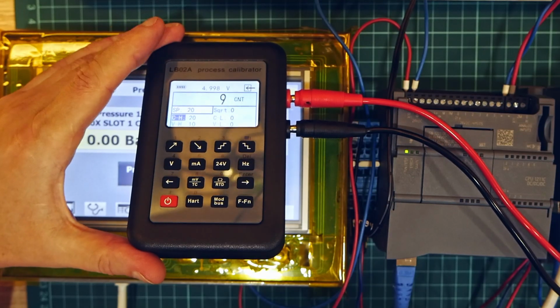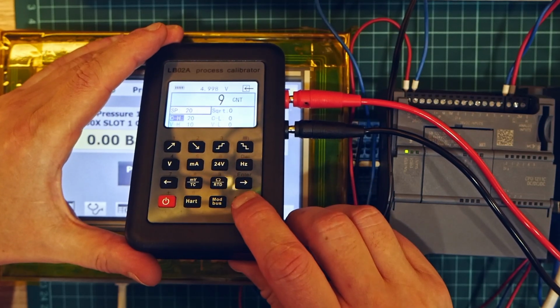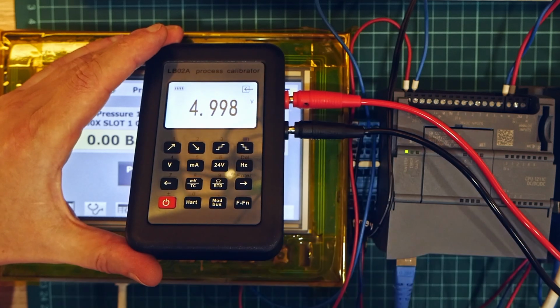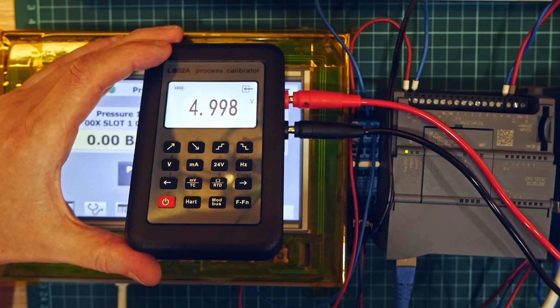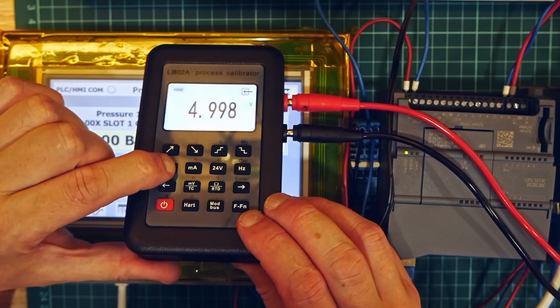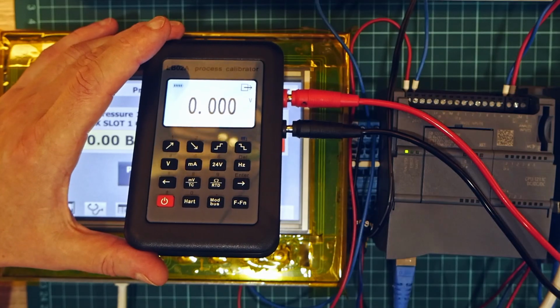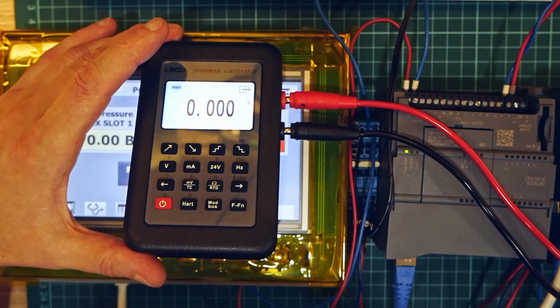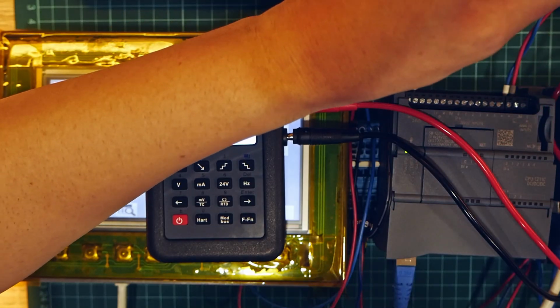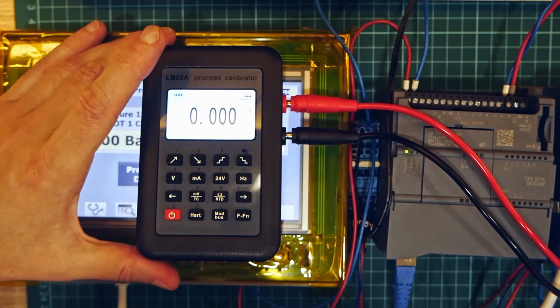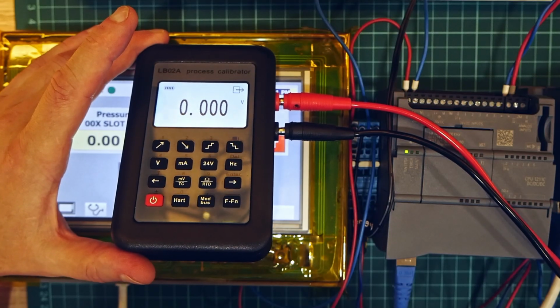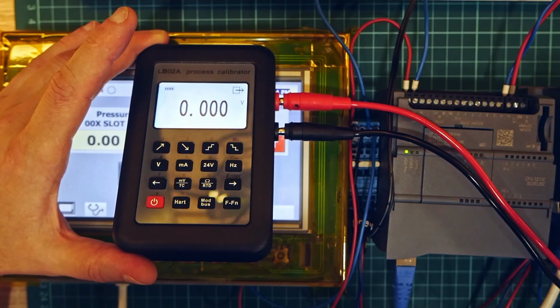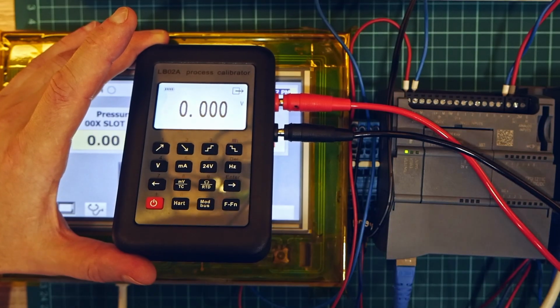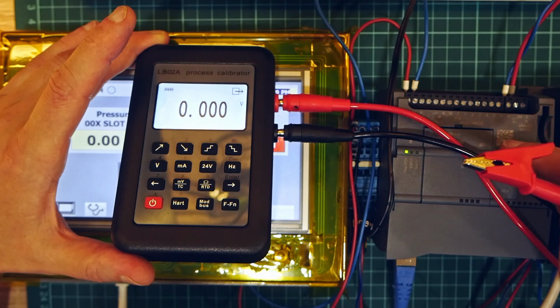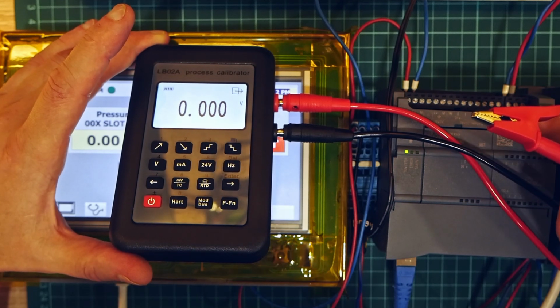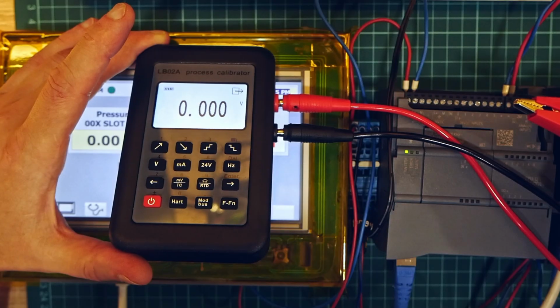Okay, so another cool thing: if we go back from function mode, right now we are in voltage measuring mode. I will press the voltage button again. Right now we are in voltage sourcing mode. Yes, so we are outputting voltage. It can output from 0 to 11 volts. So it's specifically this voltage range for PLCs that have 0 to 5 or 0 to 10 volts analog input channels.